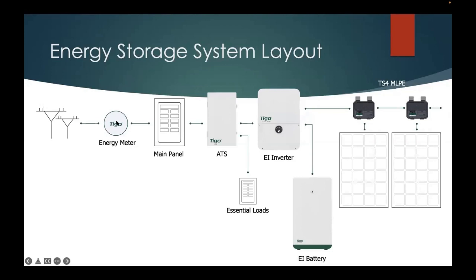So we come in from the grid to the meter to the main panel into an automatic transfer switch. From there, we go to the essential load panel, protected load panel, whatever you want to call it. We also go into the inverter, which is connected to the battery, which is also connected to the solar array. This is called a hybrid inverter because it has a battery connection and a PV array connection.